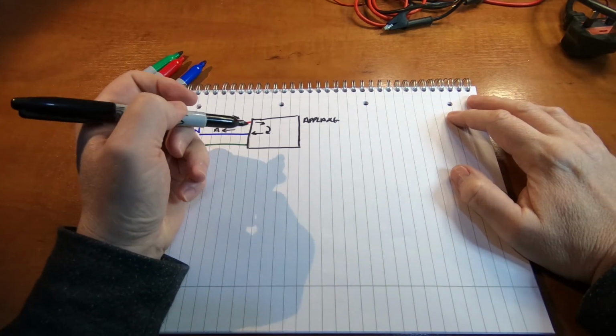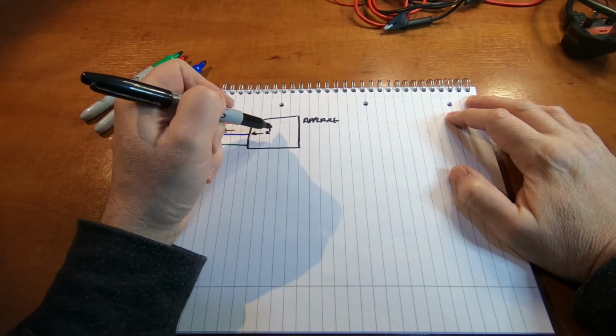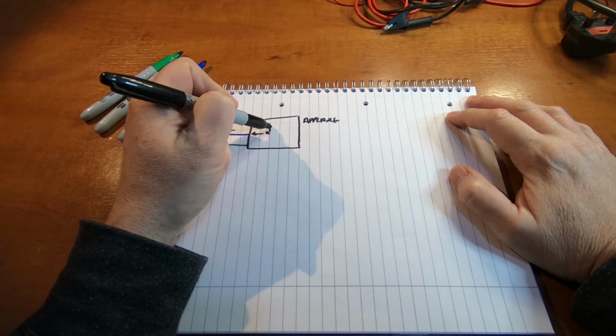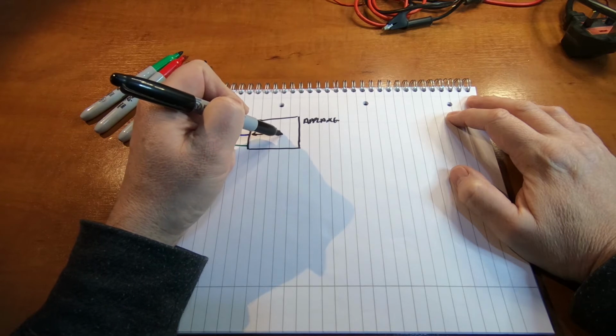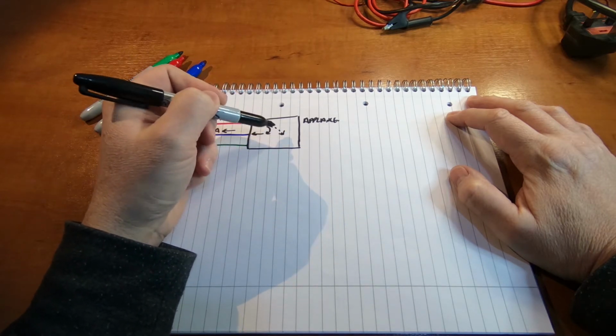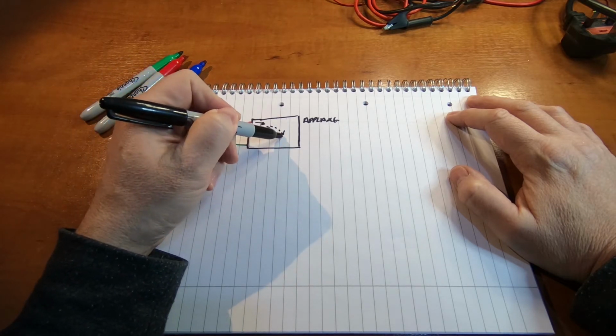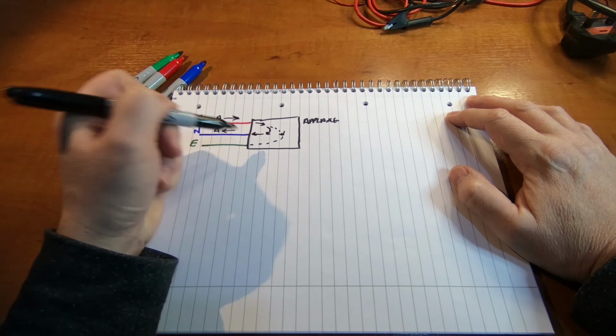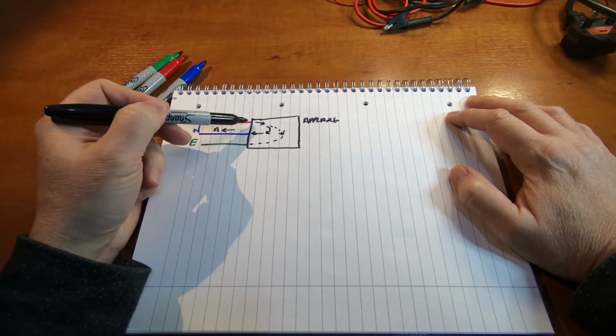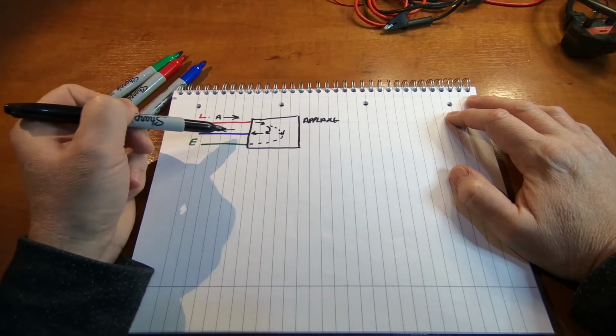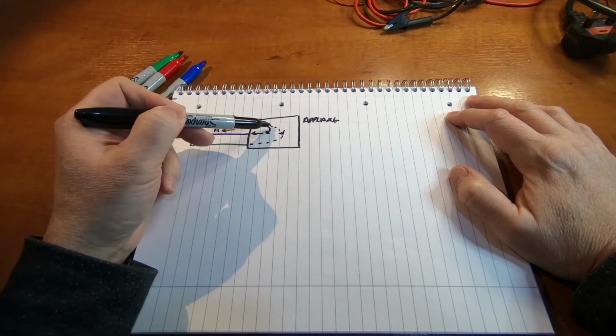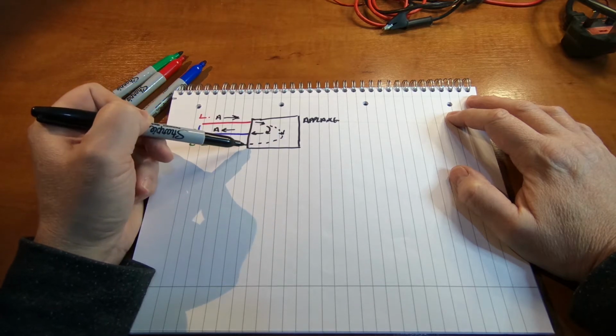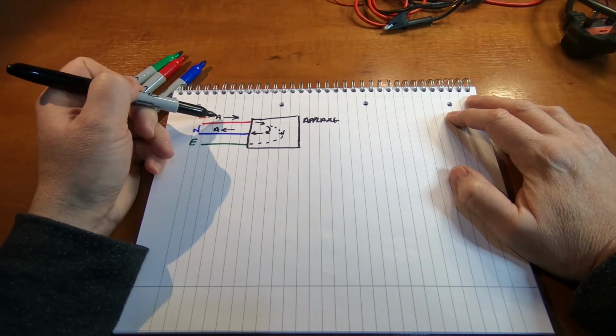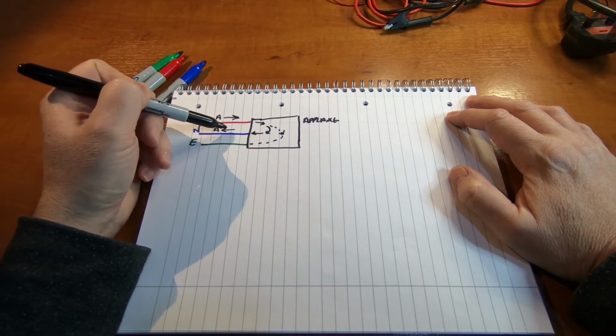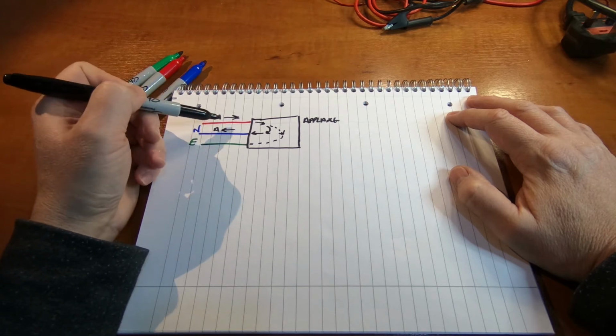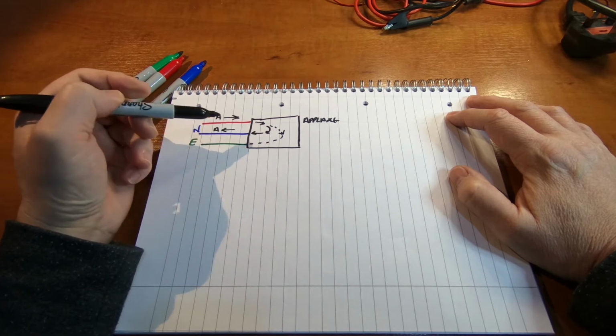Now what happens when you have some earth leakage is that instead of this being a closed loop, we have a little bit of current, so I'll mark that as just a dotted line, comes out and leaks somewhere else. Now more often than not, it leaks to the earth line like this. So now in the case of this, we have the majority of the current flowing in this loop here through the live neutral, but we also have a little bit of current branching off and ending up on the earth line. So in this case, the current going in does not equal the current coming out on the neutral line. There is a little bit less because it's split off here, and that's what the earth leakage is.